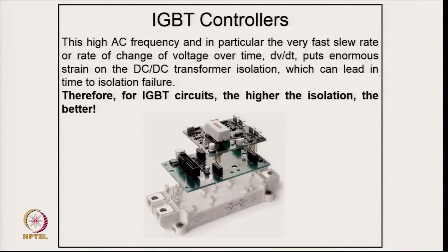Another set is IGBT controllers. As you can see from the photograph, this is high frequency, and in particular the very fast slew rate, or rate of change of voltage over time dV by dt, puts enormous strain on the DC-DC transformer isolation, which can lead eventually to isolation failure. Therefore, for IGBT circuits, the higher the isolation, the better.